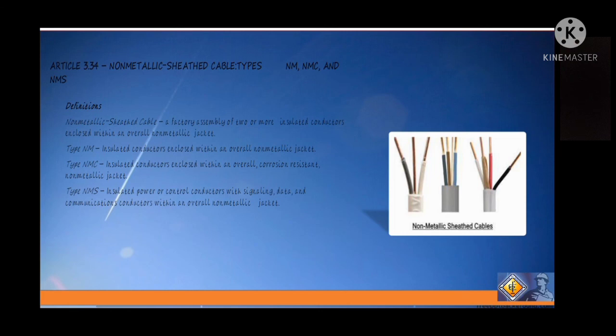Next, in Article 334, which is the non-metallic sheathed cable, which is the type NM, NMC, and NMS. For the definition, the non-metallic sheathed cable is a factory assembly of two or more insulated conductors enclosed within an overall non-metallic jacket. For the type NM, insulated conductors enclosed within an overall non-metallic jacket. For type NMC, insulated conductors enclosed within an overall corrosion-resistant non-metallic jacket. And for the last one, the type NMS, insulated power or control conductors with signaling, data, and communication conductors within an overall non-metallic jacket. We can see the picture on the right side of our slide, the non-metallic sheathed cables.